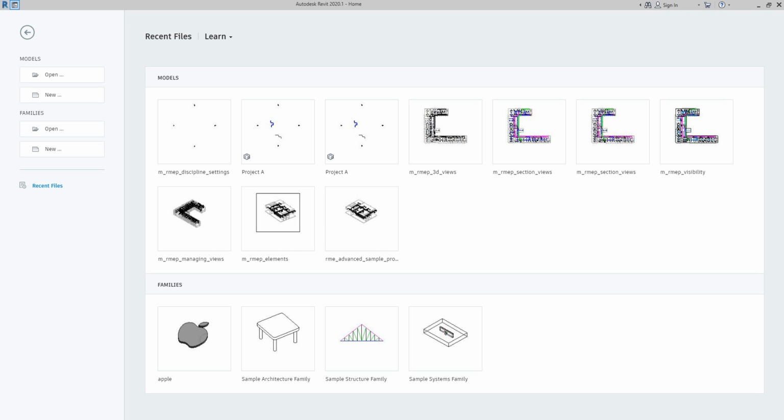In Revit, you use volumes in engineering data calculations, and volumes are defined using spaces. So spaces are very important when you do a heating and cooling load calculation. The volume of a space defines an analytical building model, which you can use for building performance analysis and heating and cooling load calculations. Spaces store values for the parameters that affect the heating and cooling load of a project.